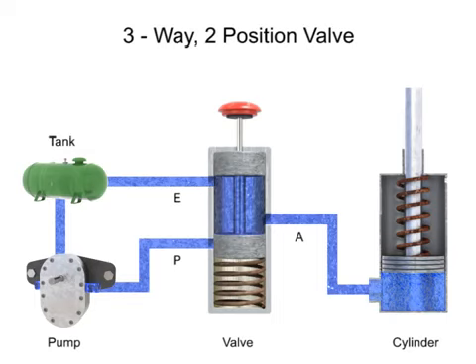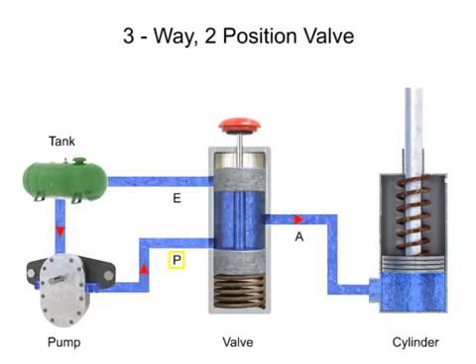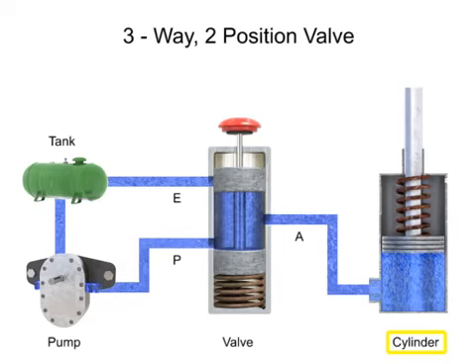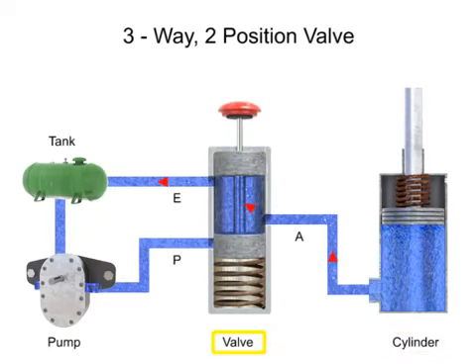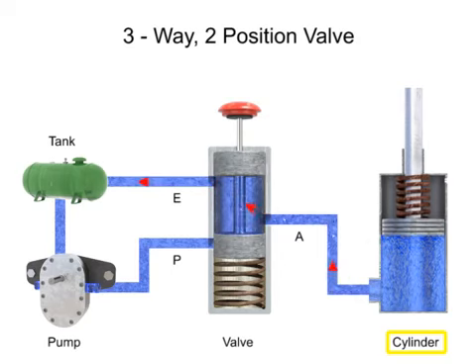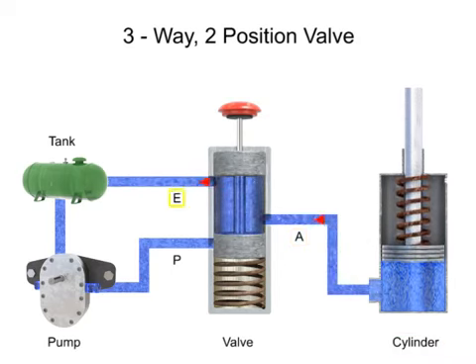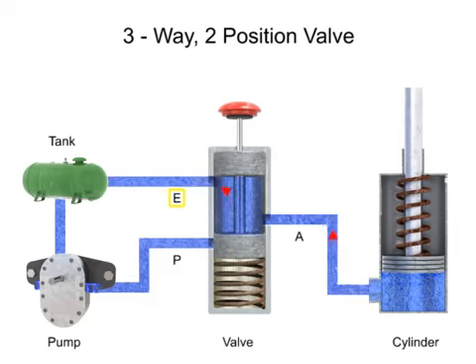Three-way directional control valves have many applications in fluid systems. One of the most common applications is for the control of single acting cylinders. In this application, fluid is pumped from a tank to pressure port P. With the valve in the normal position, fluid is blocked. When the valve is actuated, fluid flows from pressure port P through outlet port A to the cylinder. The cylinder extends and remains extended until the valve changes positions. When the valve de-energizes, the spool returns to position 1, pressure port P is blocked, and exhaust port E is opened. The cylinder retracts and fluid flows from the cylinder through port A and out exhaust port E, returning to the tank.